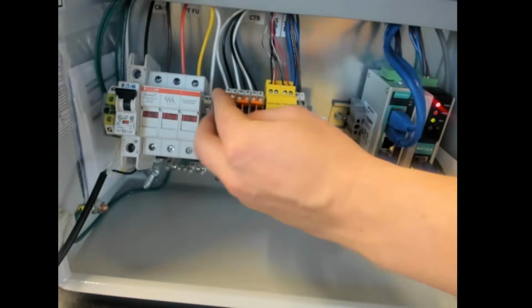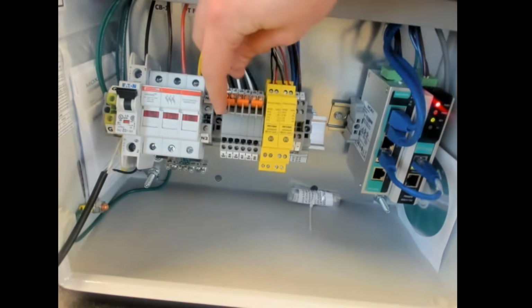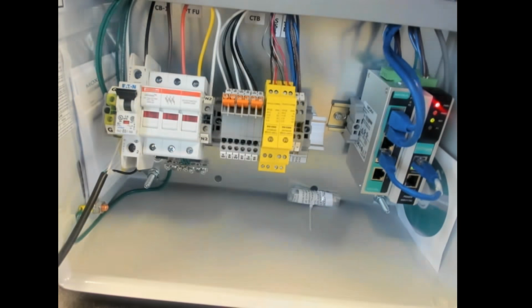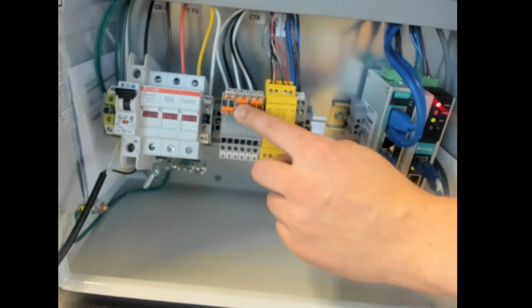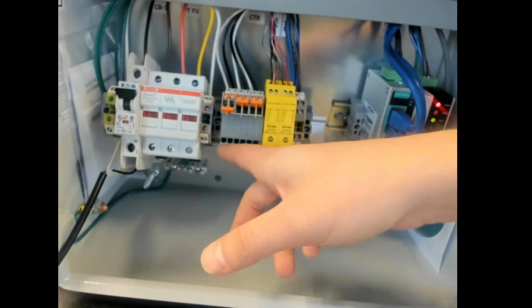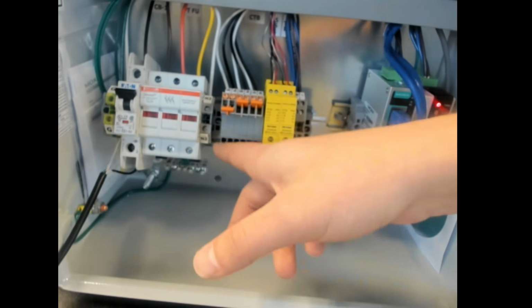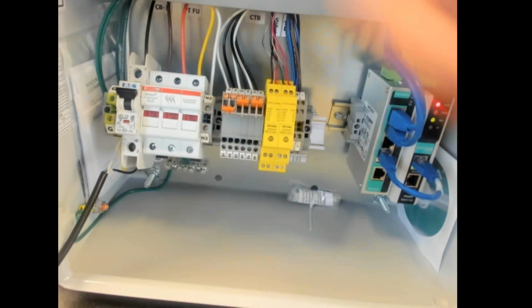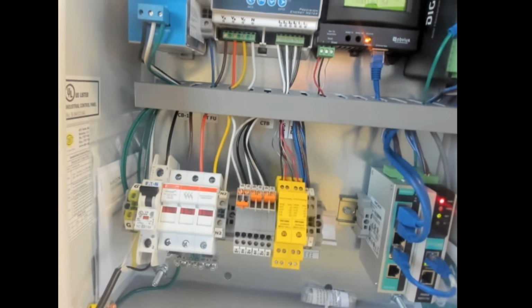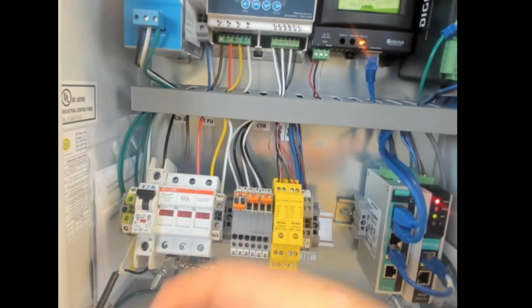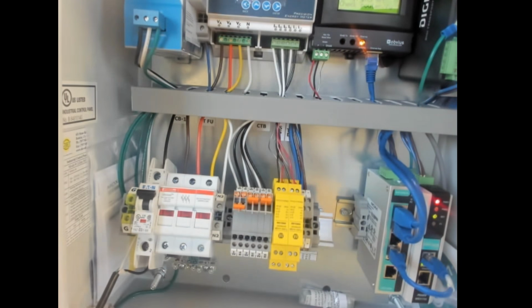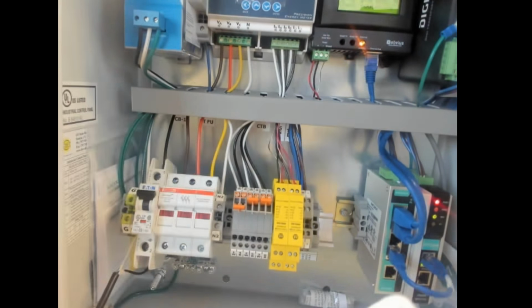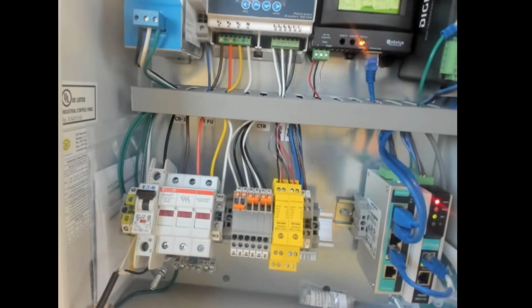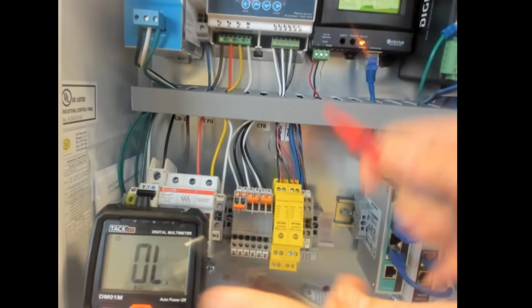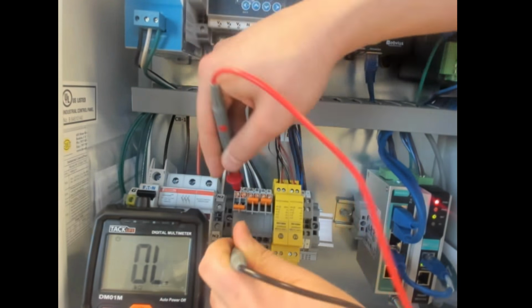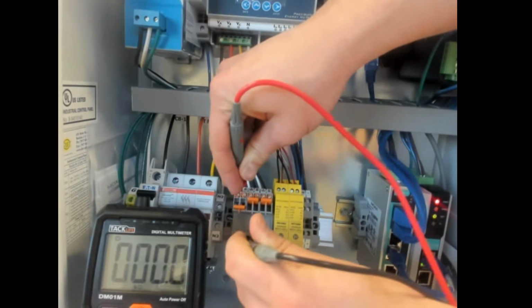So finally, the way it should be commissioned is you'll have this particular mechanism plugged in, and then you'll want to make sure that the shorting tab is in the down position. That allows us to have a closed loop between the CT and the actual meter here. So the meter will actually get measurements. Okay, so now that I have this disconnected, if I were to actually measure the resistance between the top and the bottom of the terminal block, I'll see that it's actually 0. Okay.